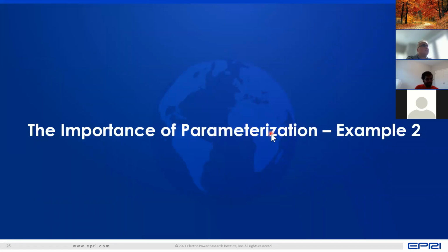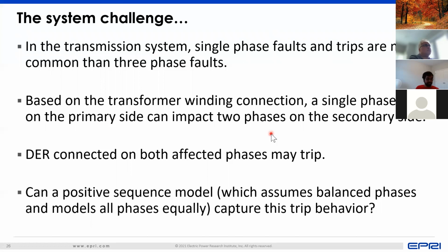I'll quickly run through another parameterization example that we have to showcase why this is important. We spoke about the transmission system and single-phase faults previously, and we spoke about how single-phase faults are more common than three-phase faults. Now, in a lot of your Power System 101 classes, you might have heard about different winding configurations of transformers, depending upon whether there is a primary side star winding or a secondary side delta winding, and so on, and how the effects of voltage and current on both sides of these windings can be different depending upon the winding configuration. We also said that positive sequence models are primarily balanced three-phase models, which means, can they really represent this imbalance that may occur because of a single-phase fault?